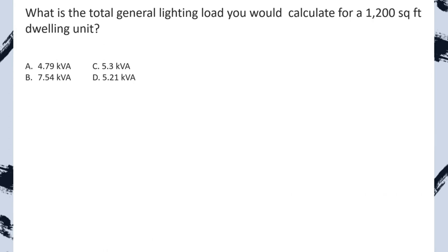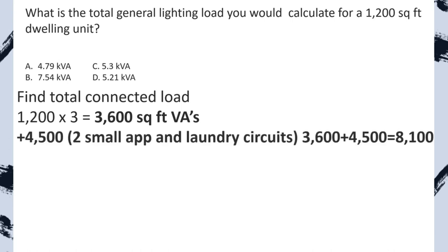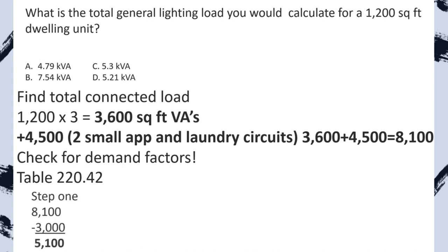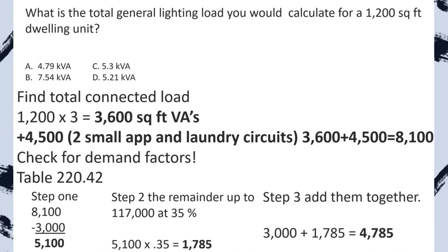Practice problem: What is the total general lighting load for a 1,200 square foot dwelling unit? Any time it asks for the total, always apply the demand factor if one exists, and always include two small appliance and one laundry circuits. Step one: 1,200 sq ft multiplied by 3 VAs equals 3,600 VAs. Add 4,500 for small appliance and laundry: total is 8,100 VAs. Check demand factors per Table 220.42: subtract 3,000 at 100%; multiply remaining 5,100 by 0.35; add them back together for a new reduced load of 4,785 VAs. We select A.